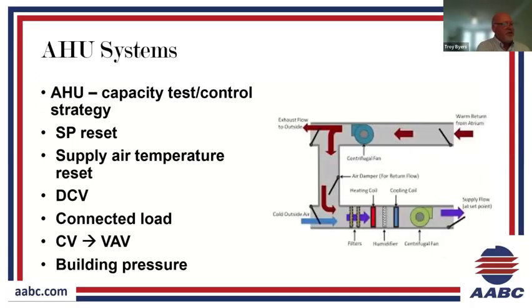So one of the things to think about when we're doing TAB in existing buildings, I should say, is there's a reason we've been called out to an existing building. Typically, there might be an issue, there might be a known load or capacity change or change in use, that we're going out there to check all of these components that we just talked about and measure and find out what's going on. So we need to have in the front of our mind that we're going to go in this existing building and start analyzing and measuring, but looking for ways that we may have to get involved in basically a recommissioning effort.